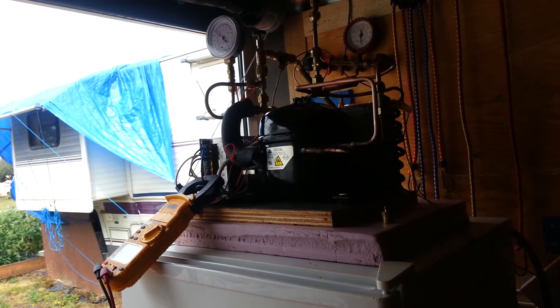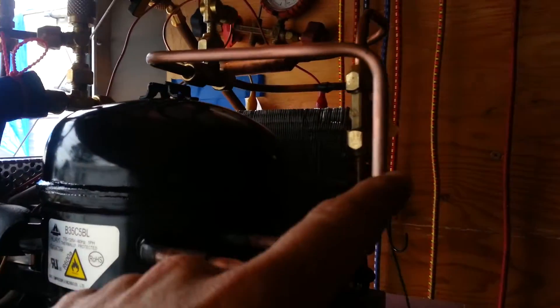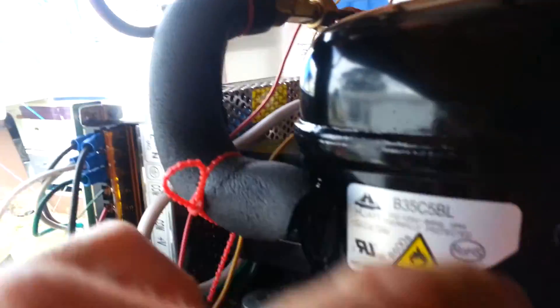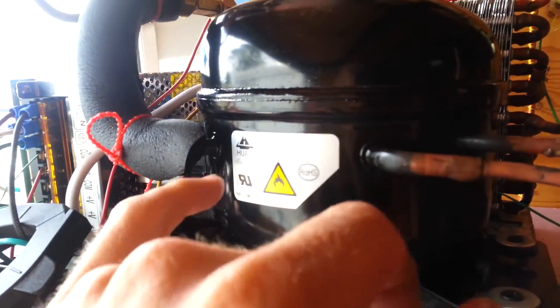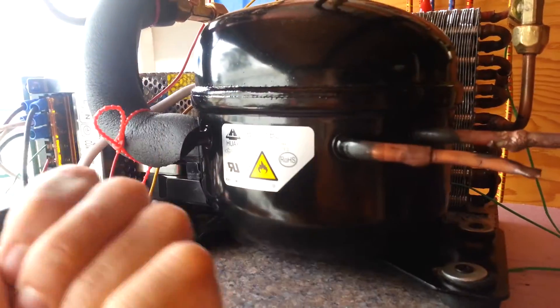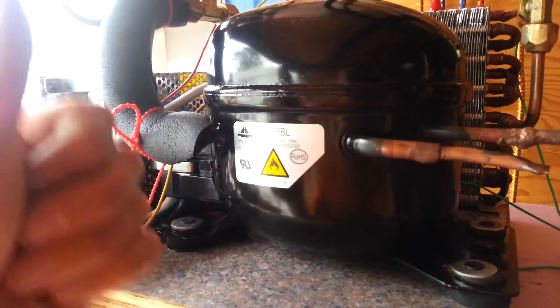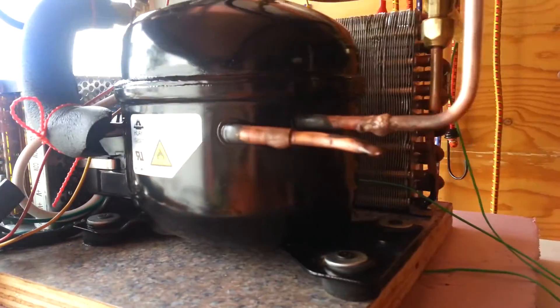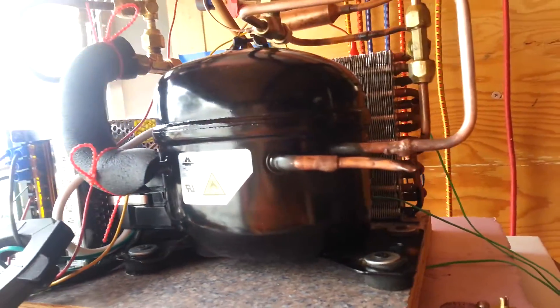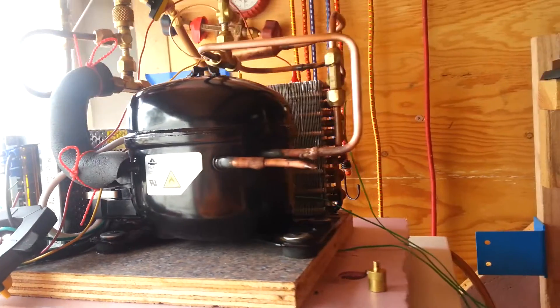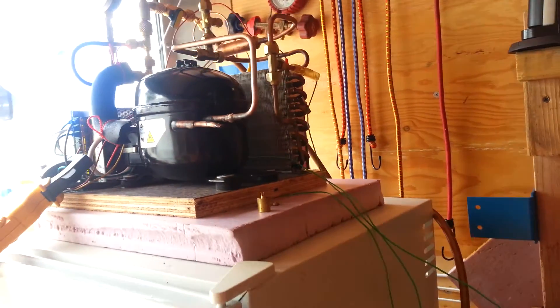I had to do a little bit of brazing this morning, a little bit of bending. I had to make that piece, and I had to make this piece to adapt because the suction and the discharge go straight out that way instead of up like the other one. So I had to do some changes there, but no big deal.